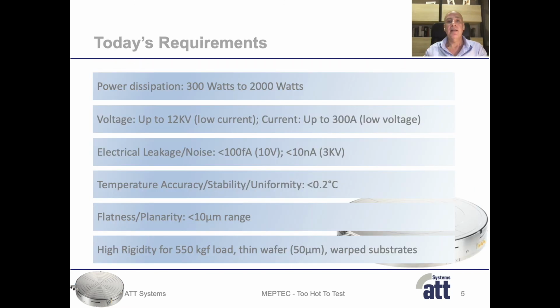The next slide shows high-level requirements that we are seeing today when a customer contacts us. Common requirements are power dissipation ranging from 300 watts up to 2000 watts, and this is the topic that we are discussing today. High voltage up to 12 kilovolt and high current up to 300 amp. Electrical leakage and noise of less than 100 femtoamp at 10 volt and less than 10 nanoamps at 3 kV. Of course, temperature control performance like accuracy, stability, and uniformity. Mechanical requirements like planarity of 10 micron and high rigidity up to 500 kilogram force.